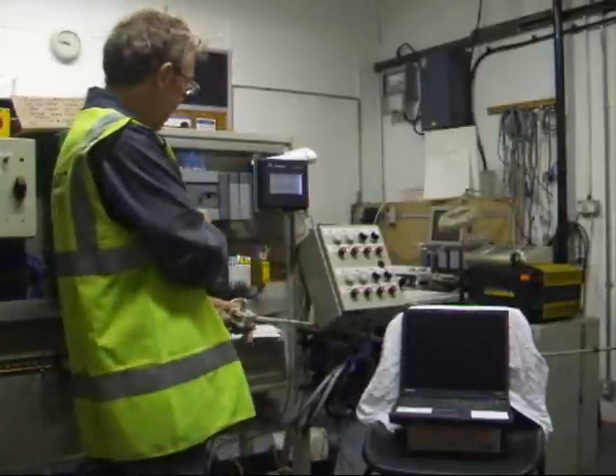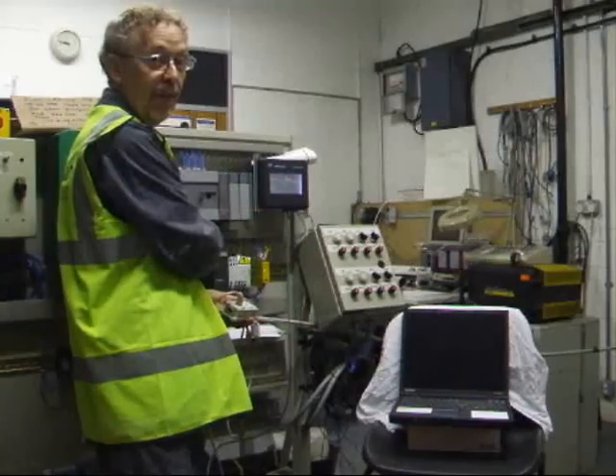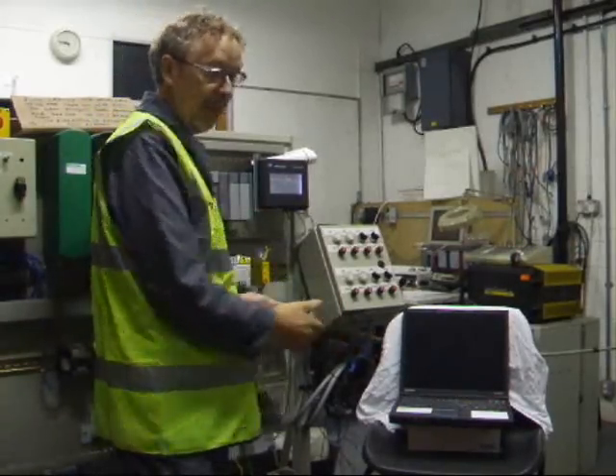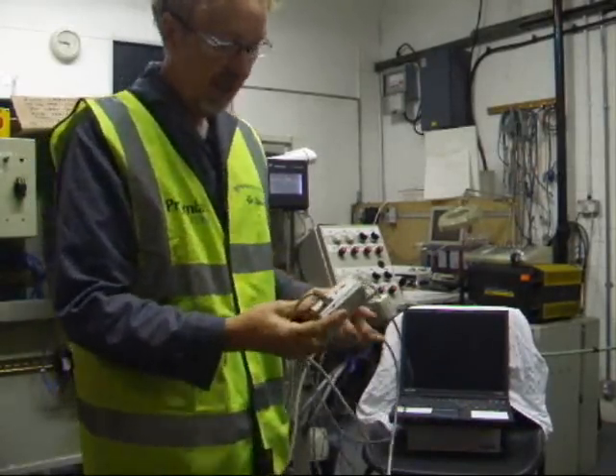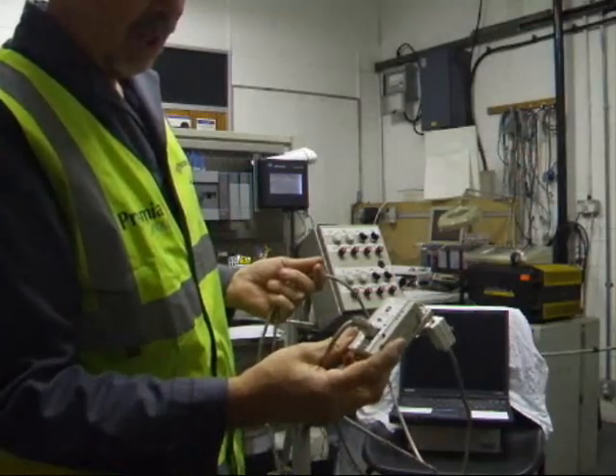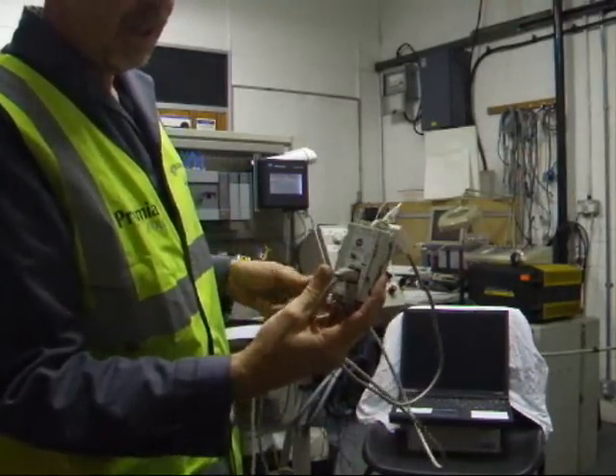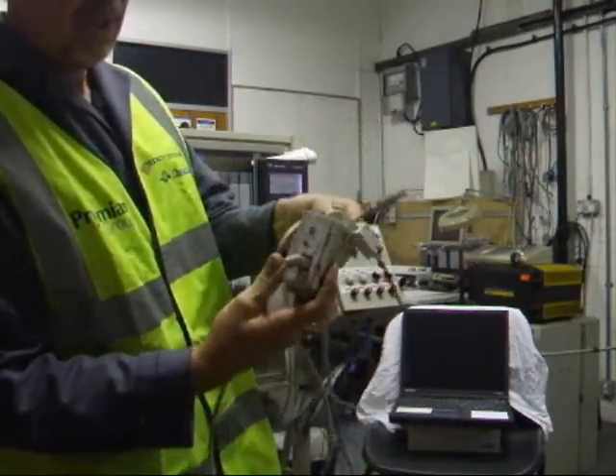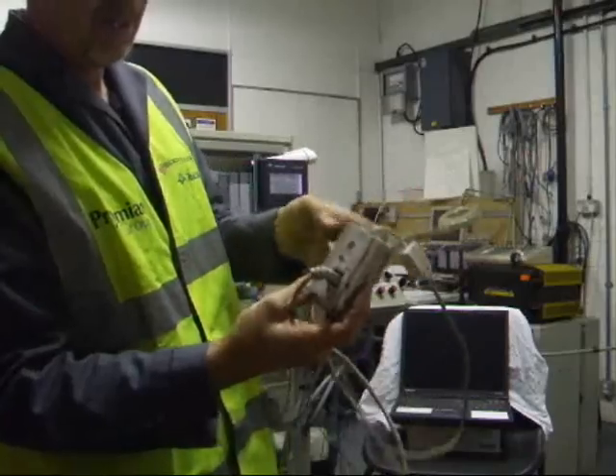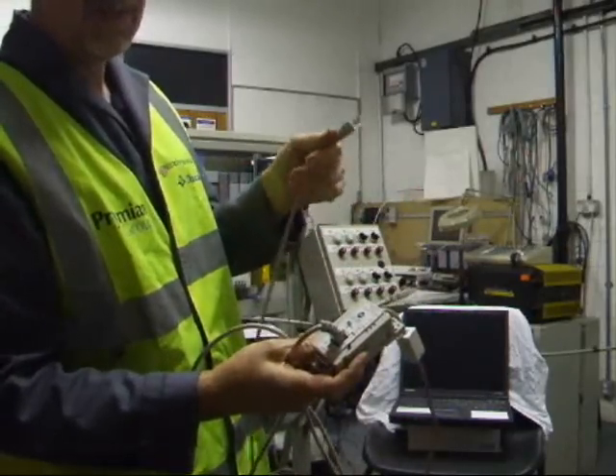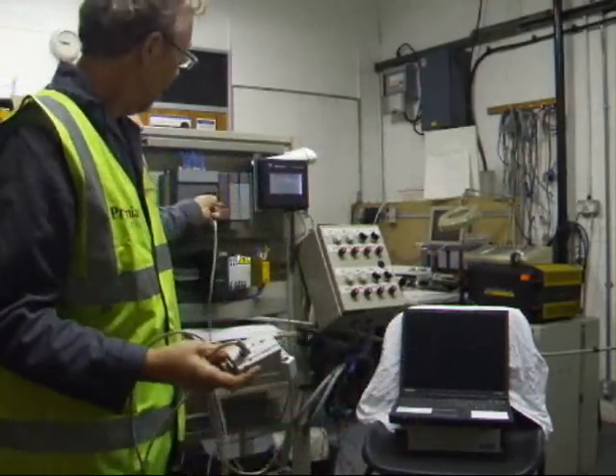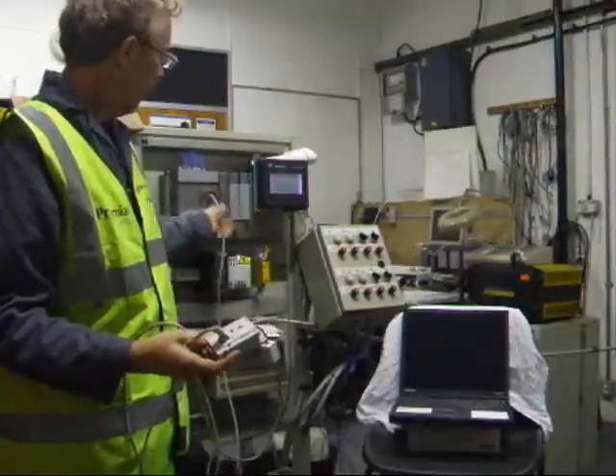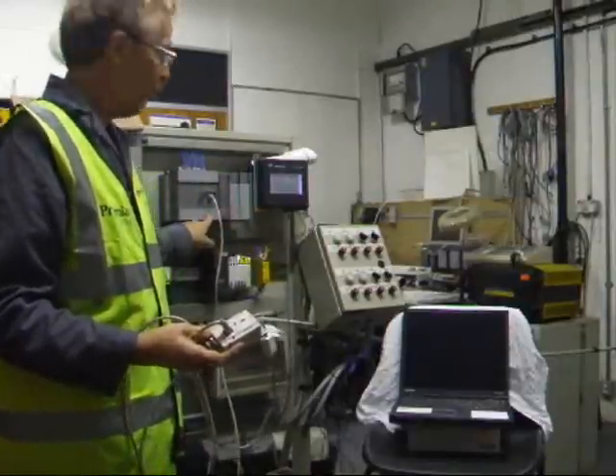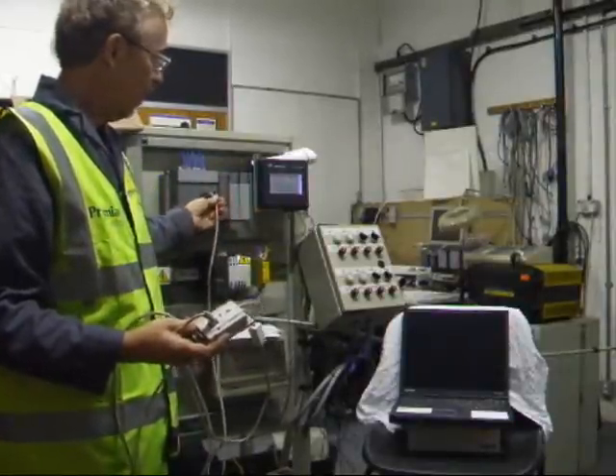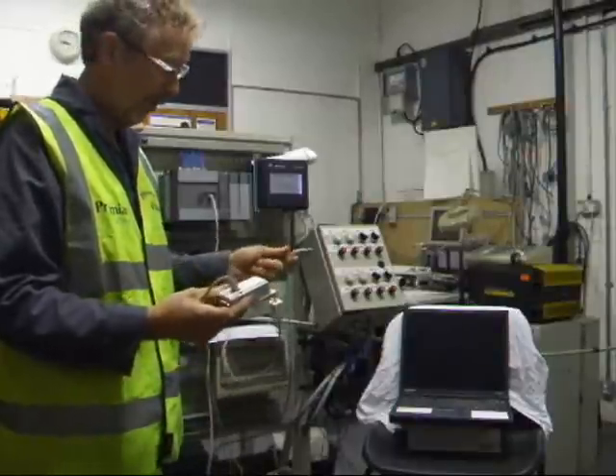Today I'm going to connect the Allen Bradley SLC 500 PLC to my laptop. And I'm going to be using this converter. It's a 1747 UIC. It connects into your laptop with a USB plug. And the other end is a DH485 which goes into the PLC. This PLC only has one socket, DH485, so that's the only option on that one.